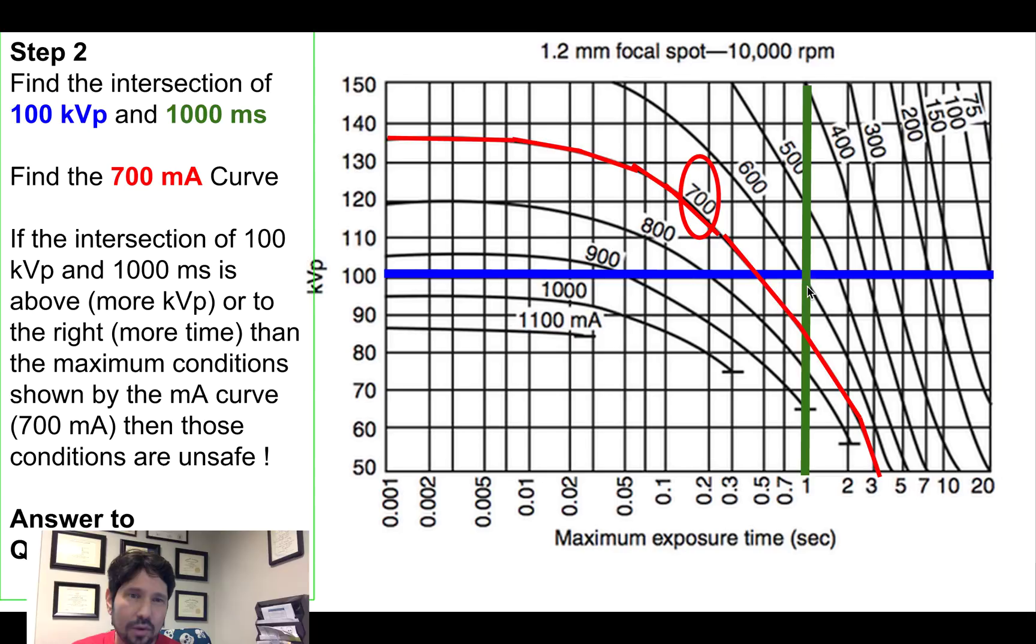So that's the point we're going to say is that above the curve or below the curve. So the curve would say at 100 kVp, I can only go about 0.45 seconds. Anything above that is going to be unsafe. And so here we see we're asking for a second. The curve says, no, I can't go past this cutoff at that kVp. So if we're to the right of the curve, or if we're above the curve, we're unsafe. Alright, so these conditions to this question would be unsafe.